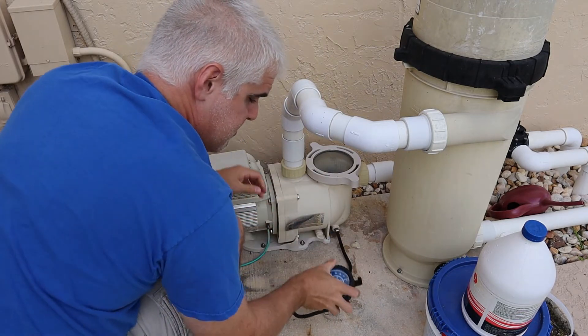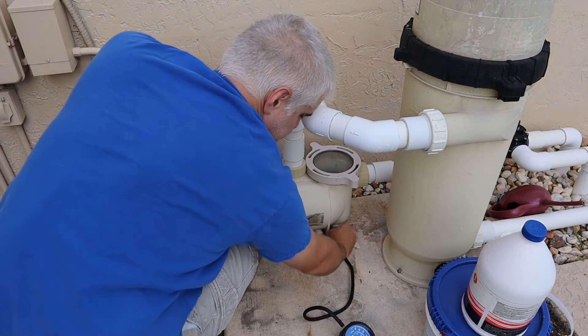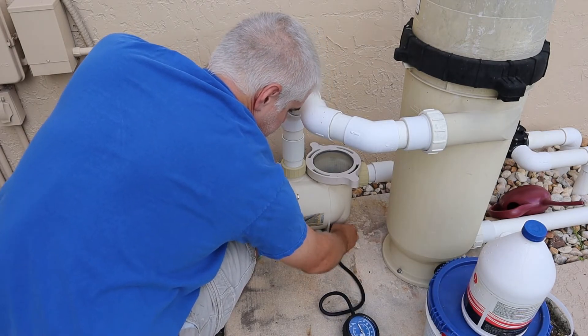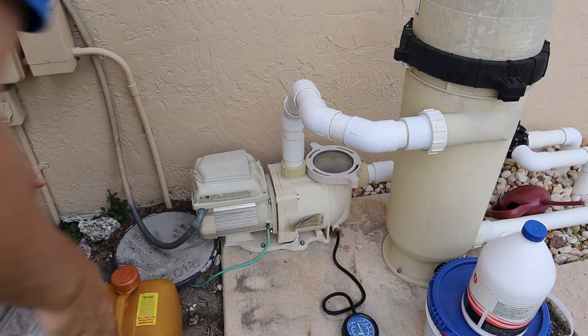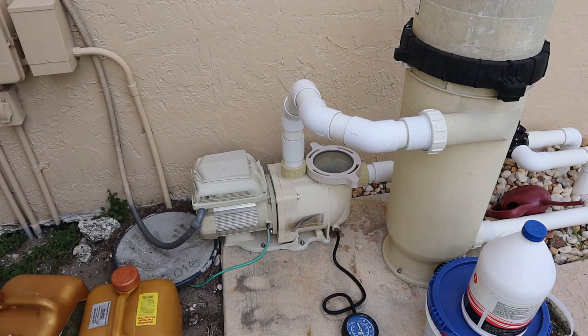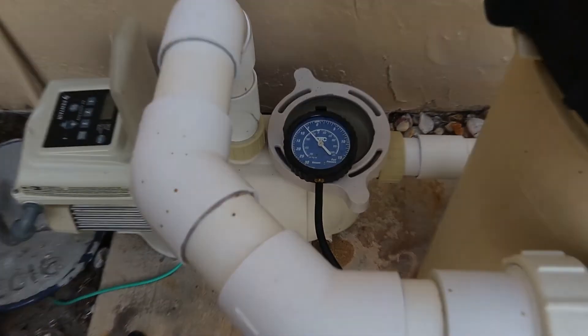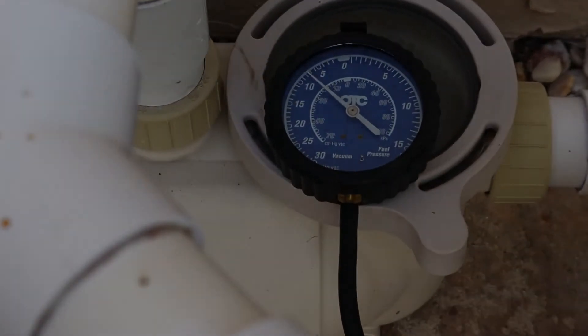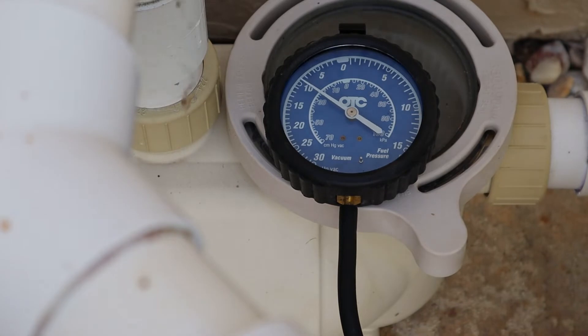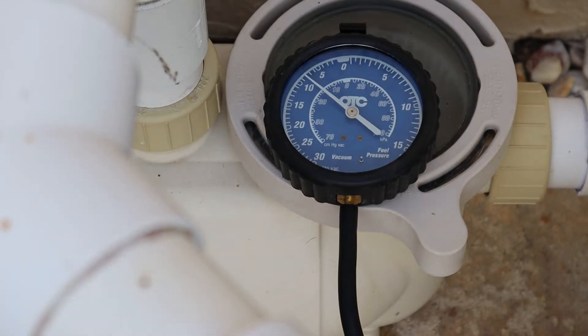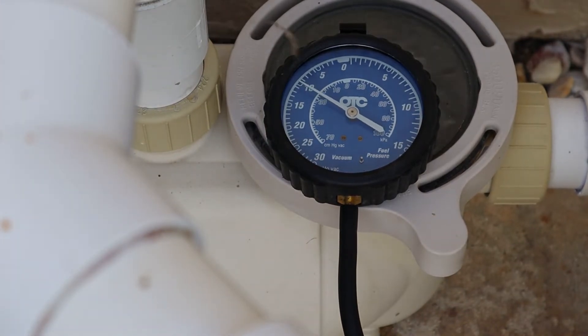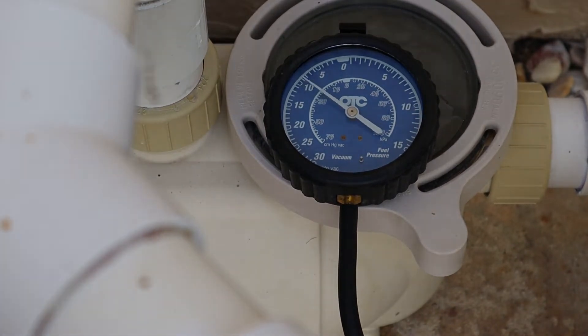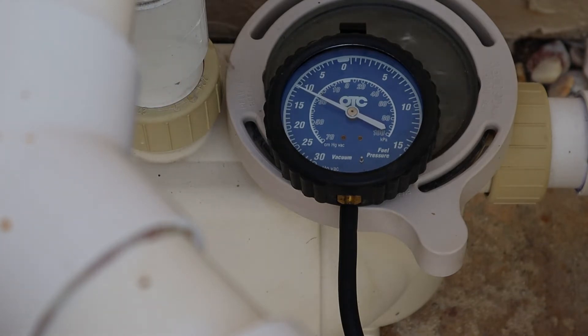I got everything hooked up and just turned the pump back on. There's the vacuum gauge right there. You can see it's still dancing around because it's got some air in the lines. It's probably going to settle somewhere between 10 and 15 inches of mercury.